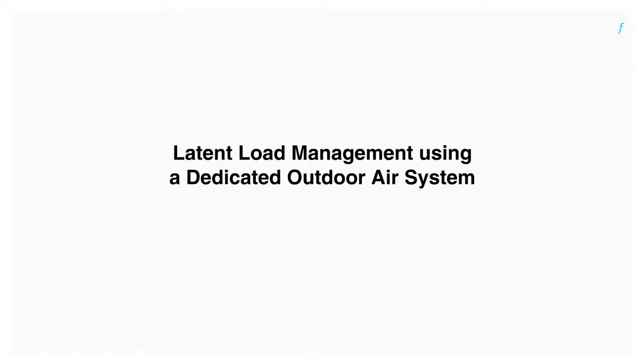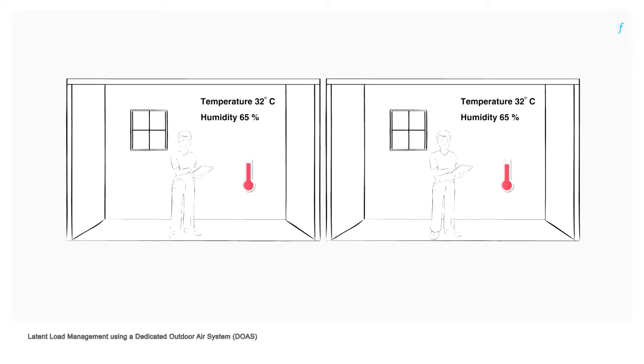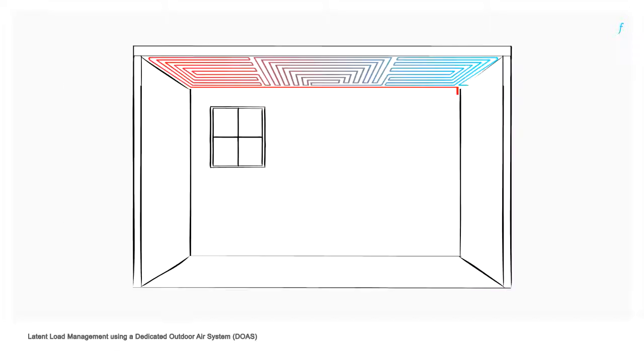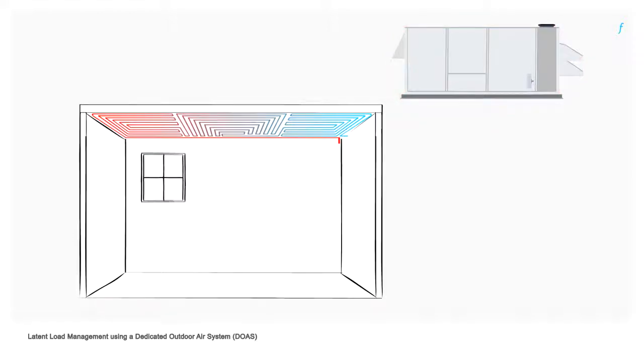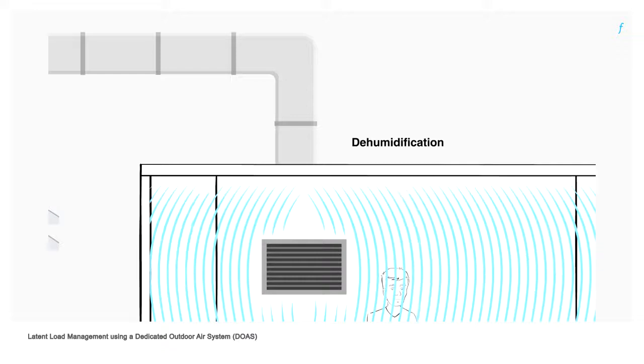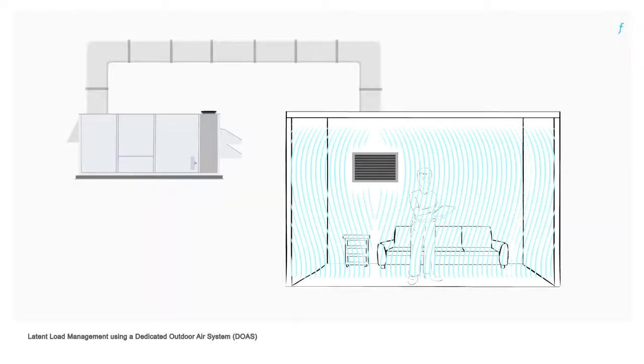Latent heat load management using a dedicated outdoor air system. Comfort is as much about humidity as it is about heat. While radiant panels take care of the heat in the air, a dedicated outdoor air system is essential to handle humidity in the space. Along with dehumidification, the dedicated outdoor air system accomplishes ventilation and filtration. The air quantity requirement in this system is much lesser when compared to a typical air-based cooling system.